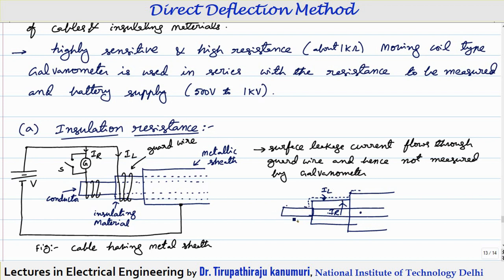If you directly connect the galvanometer and measure — for example, connecting the positive terminal here and the galvanometer directly connected — whatever current passes through the galvanometer will be the sum of IL plus IR. That means whatever current is measured by your galvanometer is the total current. Actually, we have to measure only the value of IR to know the insulation resistance.